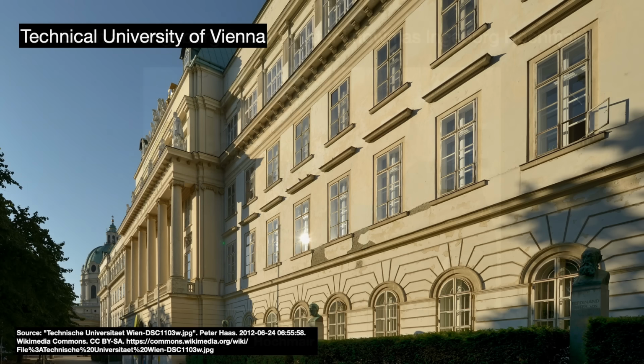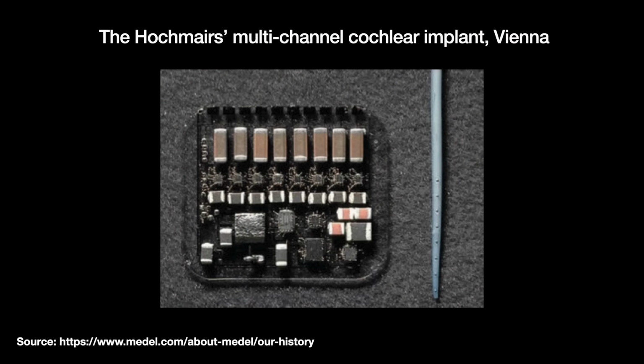By December 1977, they built an 8-channel electrode device that sampled sound, split it into 8 frequency bands, and then fired pulses corresponding to those at a rate of 10 kilohertz, quite advanced. The concept behind the 8-electrode device was sound, but it did not work quite well in practice. The 8 channels suffered too much crosstalk. Subsequent speech tests found better results with devices having fewer electrodes and channels.